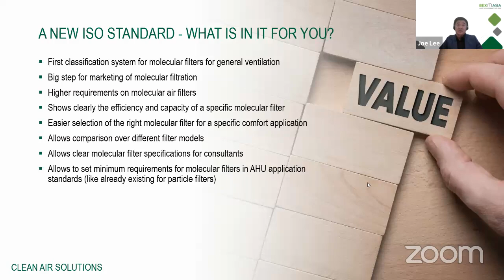Like I mentioned earlier, in the past when a consultant would spec for molecular filters, it's just: do we need molecular filters? Yes, we need them, but what kind of efficiency, what kind of classification, was unknown. So with this standard, you actually bring things more definite and clear to the industry - what kind of gases you want to target, and what kind of classification you want. And of course, you set a minimum requirement for molecular filters in AHU applications, just like the existing particle filters using the ISO 16890 standard.